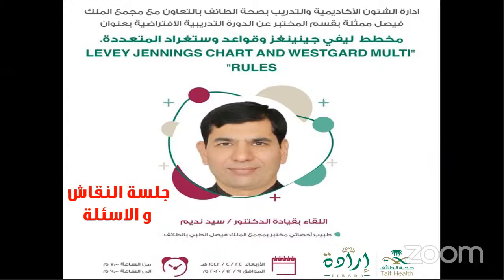Similarly, you have a multi-rule wherein you look at the overall graph, not just the daily run. You look at the overall graph. If you can find any trends, that means your system is gradually deteriorating. You need to look at a trend, or you need to look at shifts in the mean, and you will solve according to that issue.